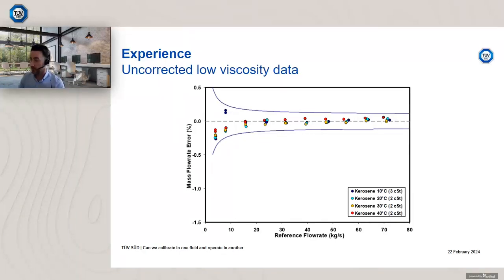So this slide here is the results for a Coriolis meter with respect to a low viscosity fluid similar to kerosene. So it's a mineral oil with fluid properties very similar to kerosene. So density around 750 to 800 kilograms per meter cubed, and viscosity in the range of 2 to 3 centistokes. We have 4 sets of data here.